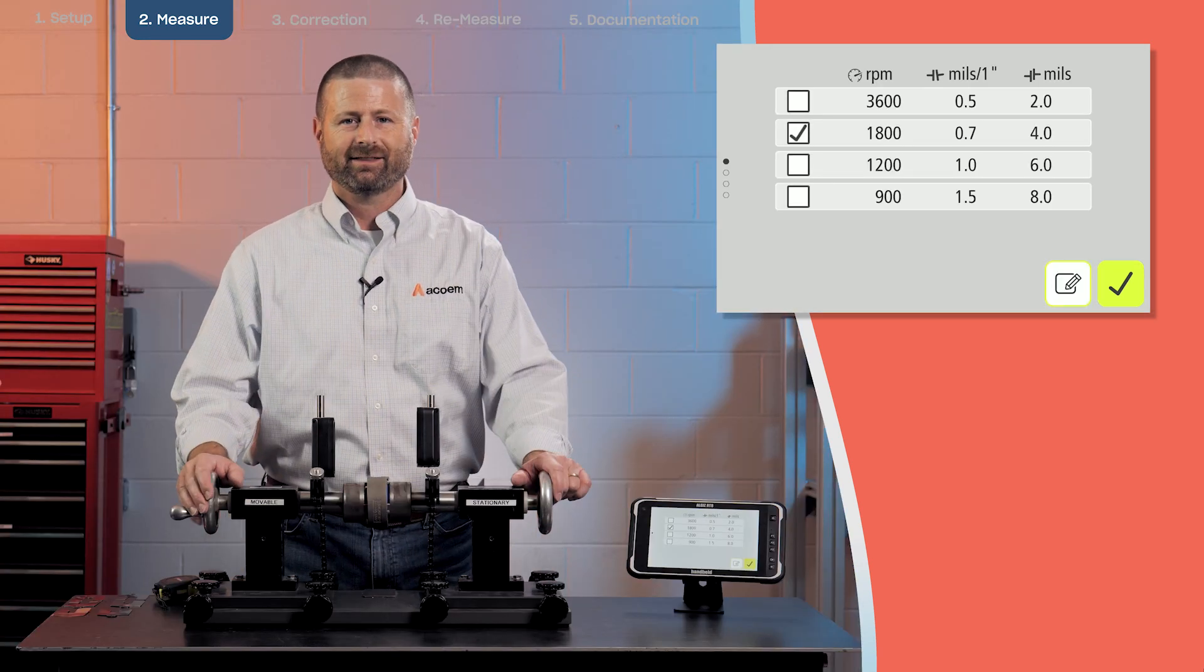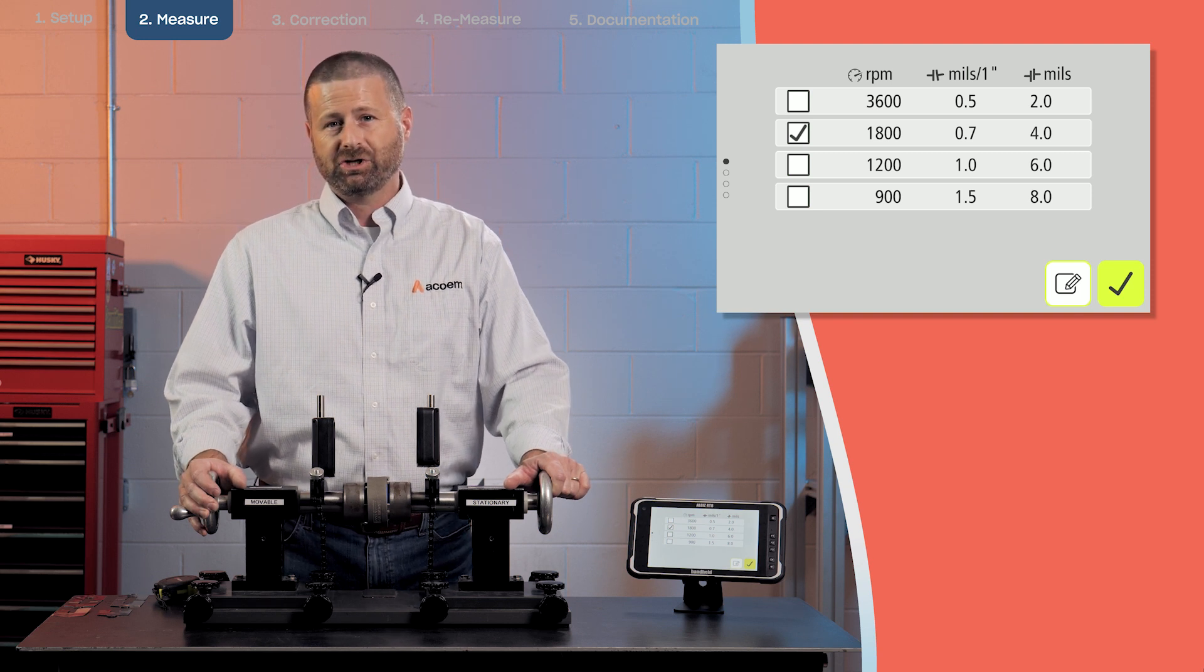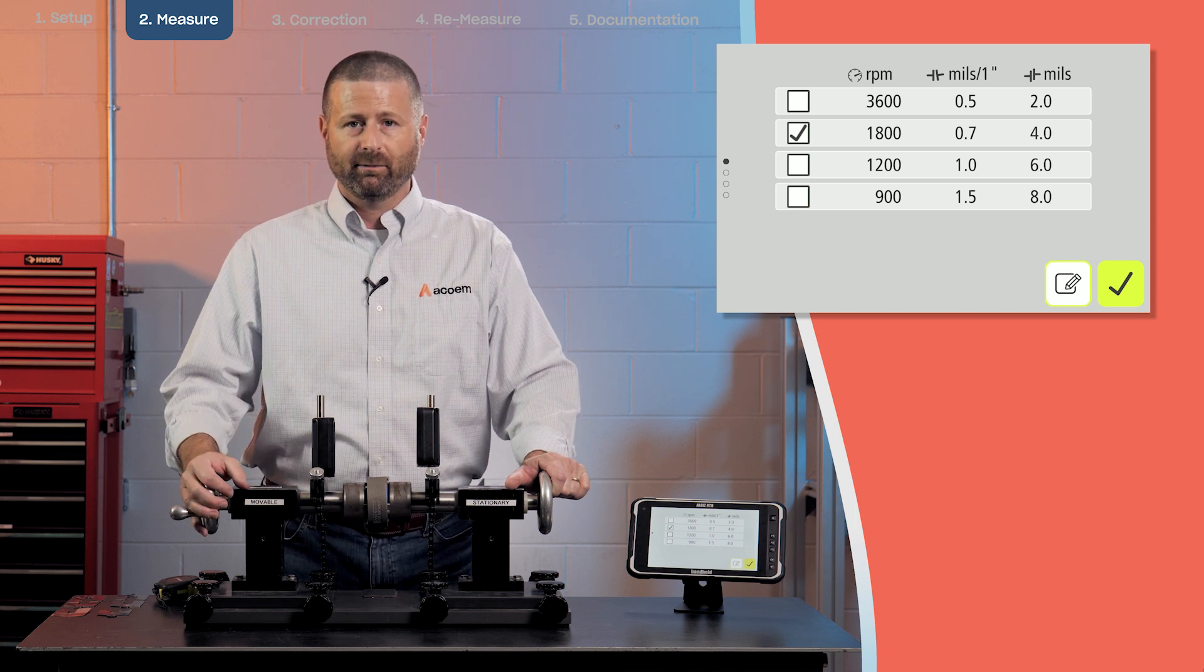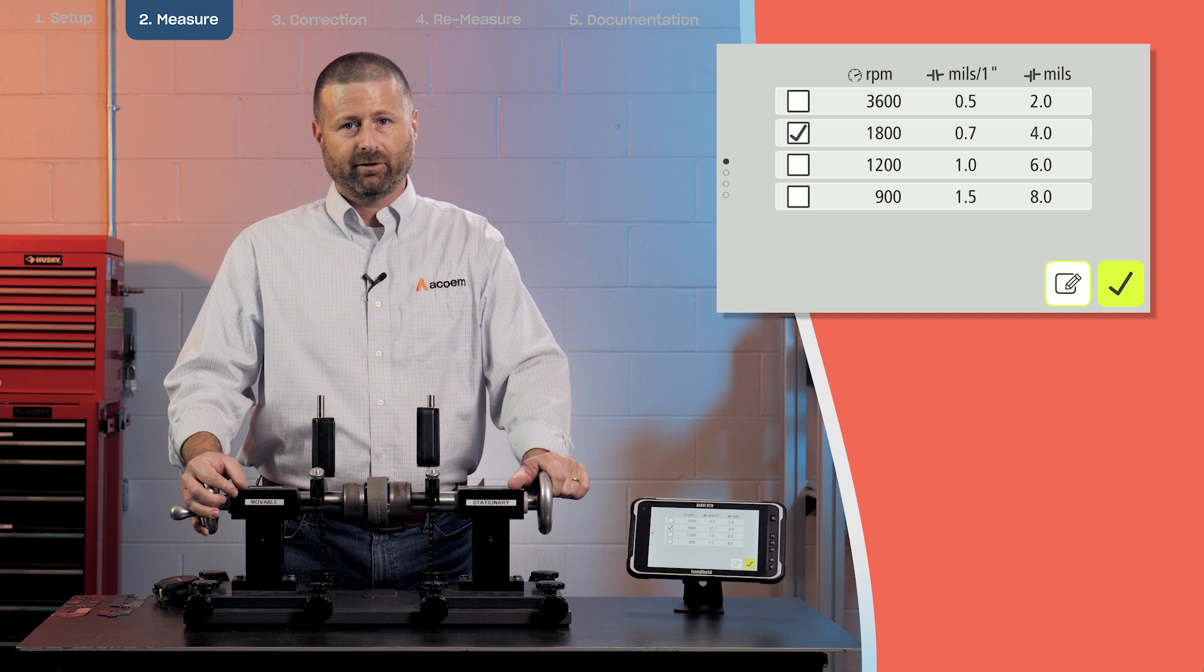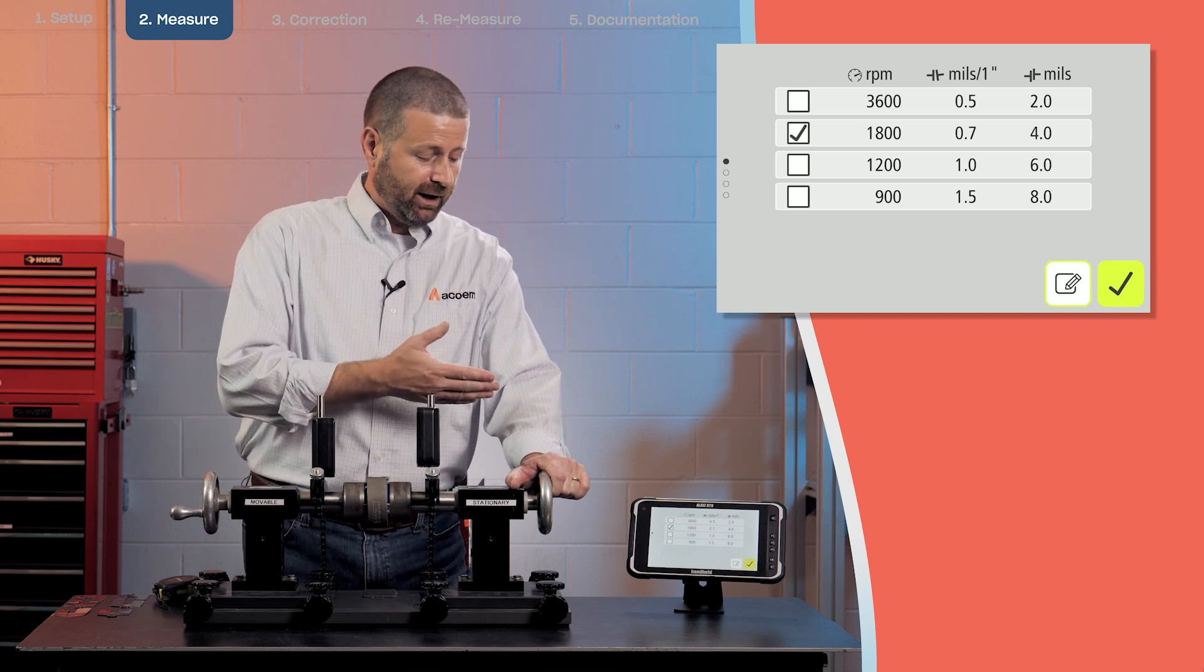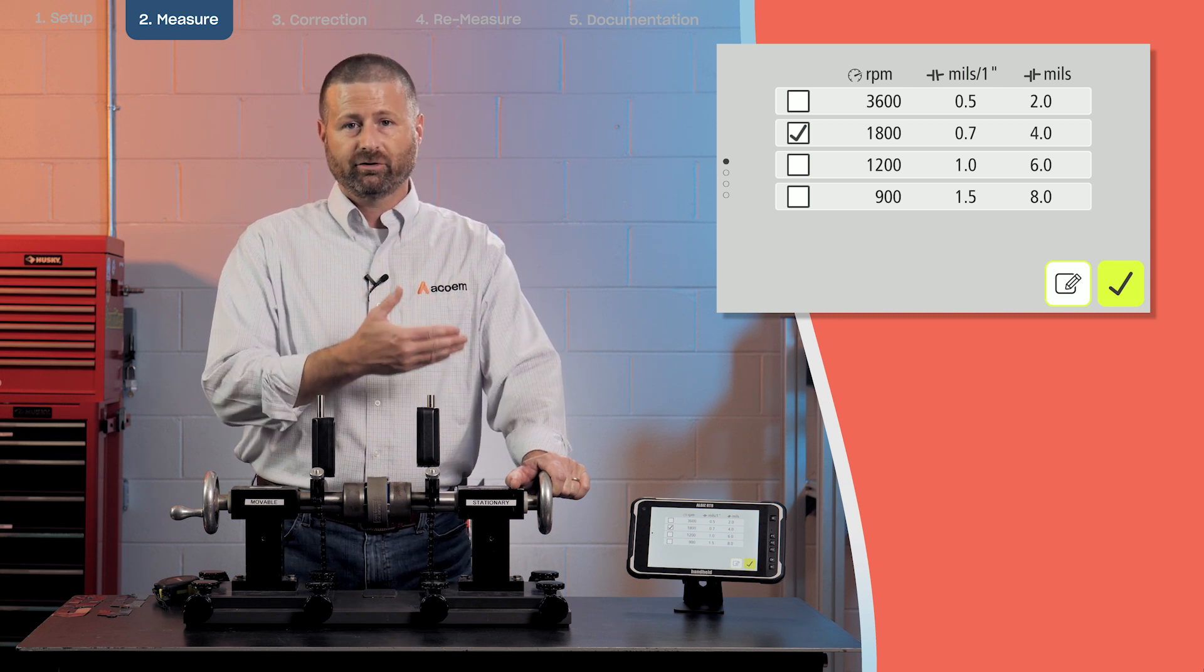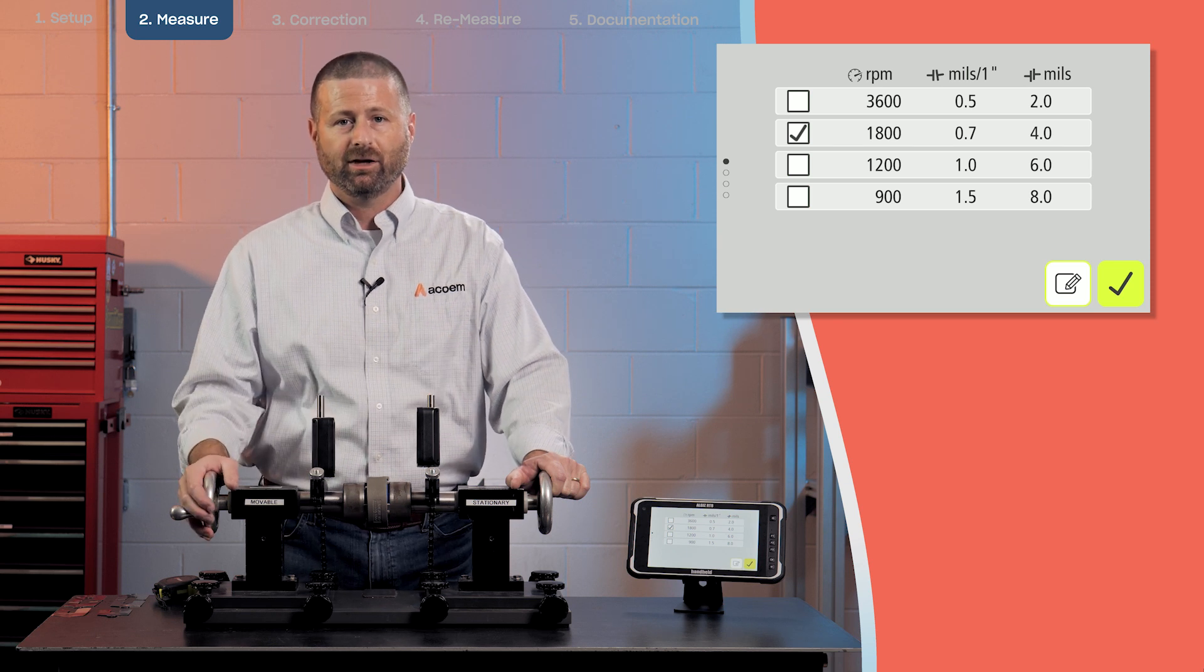Next I'm going to select the tolerance for my alignment. Tolerance is generally based on machine speed. The faster a machine rotates the closer we want to be with our alignment tolerance. I will select 1800 RPMs for this alignment and our chart has four selections. If you want to use your own selection for a tolerance there is an opportunity to input a user tolerance.